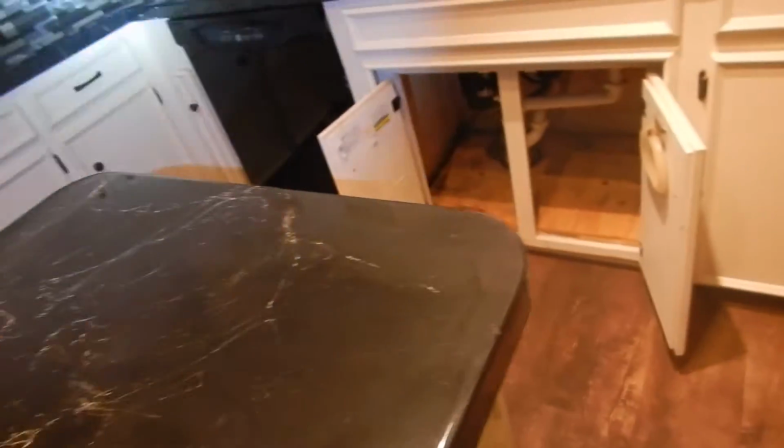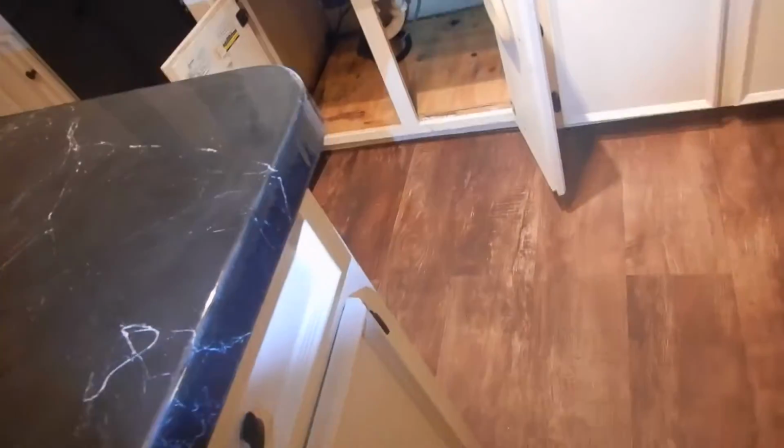And then we got our cooktops, and the thing about the electrical in this kitchen is that none of these are GFCI protected. And underneath here, we've got open electric junctions, and the conduit's not connected really good. I wasn't able to operate the dishwasher because I could not open the door, do no harm. Third horsepower garbage disposal, we can just do a dry run, and it's locked up, it's seized.